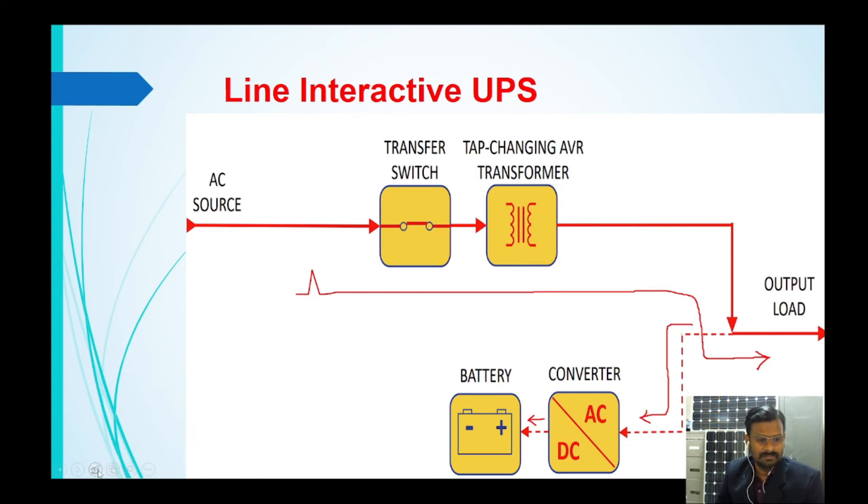During power failure, the power which is coming from here is going to be stopped and instantaneously the power will be fed from the battery in this direction. Now the converter is going to act as an inverter and then feed the load. The change over time for this is going to be very very less or you can say there is no change over time.